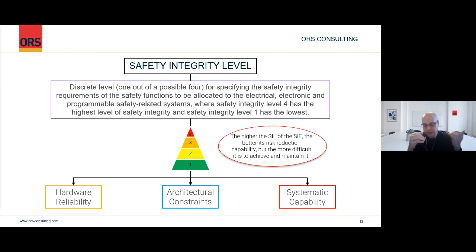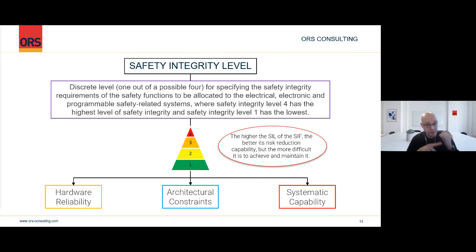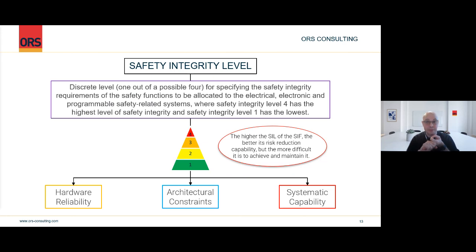SIL is not a probability of failure on demand — probability of failure on demand is part of SIL, but it's not all of it. To achieve SIL, you need three things: hardware reliability (that is, your probability of failure on demand), architectural constraints (how many redundancies you have in your safety instrumented function in each of the elements), and systematic capability (whether you are controlling all the potential systematic failures which could occur within the safety instrumented function).